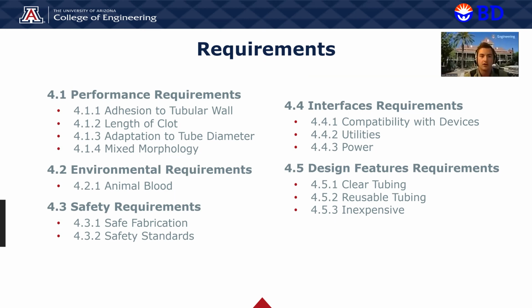As well, here are the requirements. We split up requirements into 5 different sections: performance, environmental, safety, interface, and design features. But the section of the requirements I want to focus on is 4.1, the performance requirements, which were given to us specifically by our sponsor: that the clot thrombus needs to adhere to the tube wall with a length of 10 centimeters, adapting to diameters from 3mm to 10mm, and have some mixed morphology present in the blood itself.